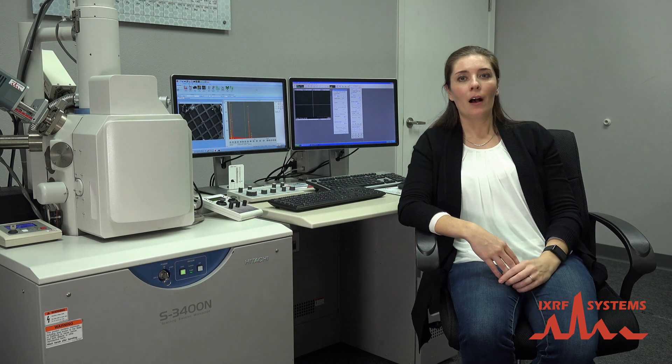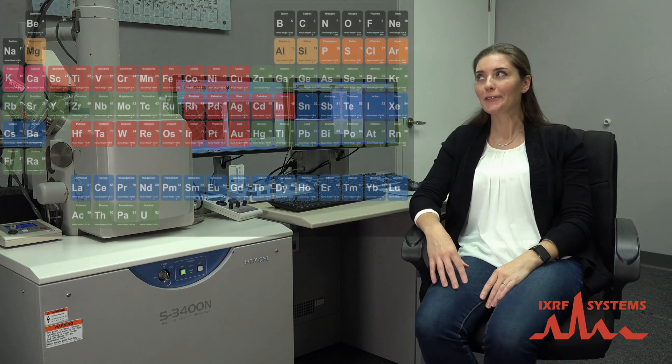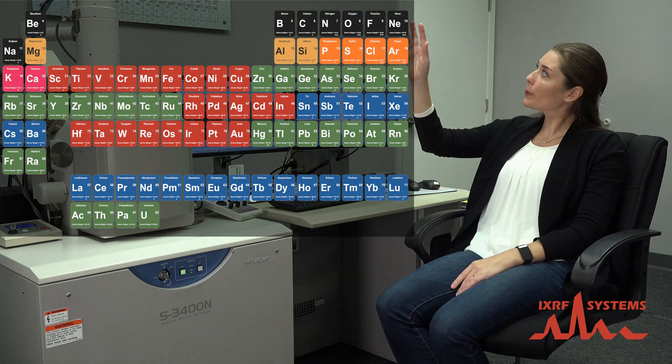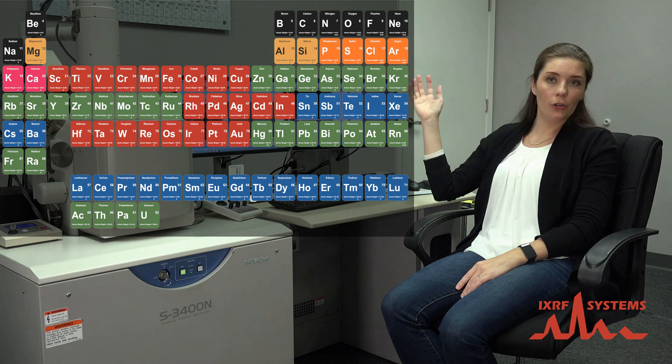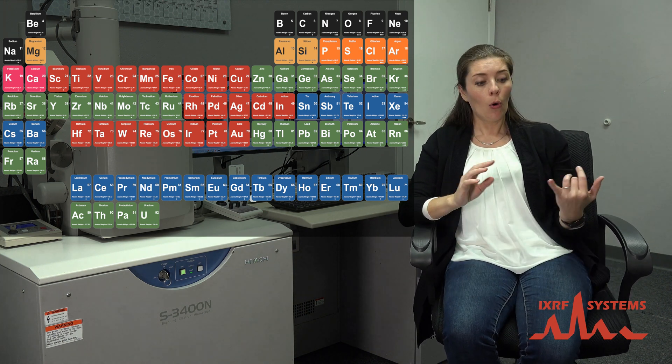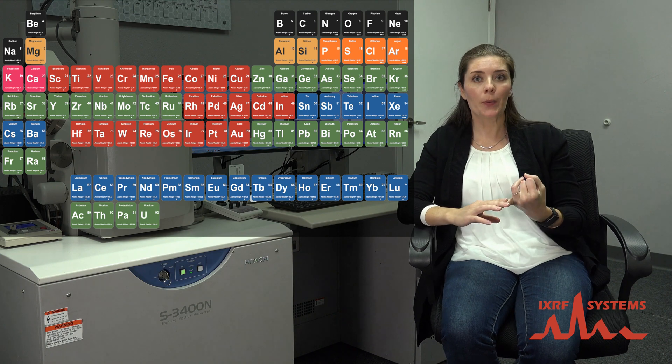So what elements can we see with this technology? That's always a tricky question. The short answer is almost all of them. We can see essentially from beryllium up to uranium, but what we can see is always very much dependent on what's in your sample, what elements are present, and what else is in there — what we would call matrix.